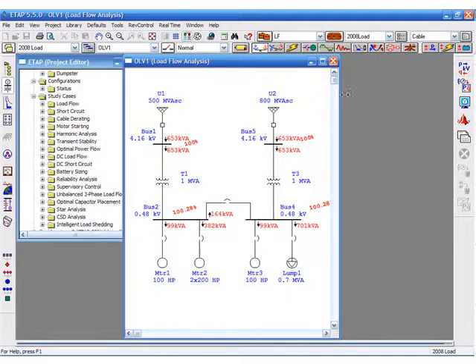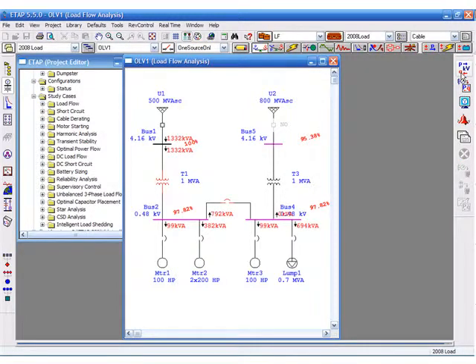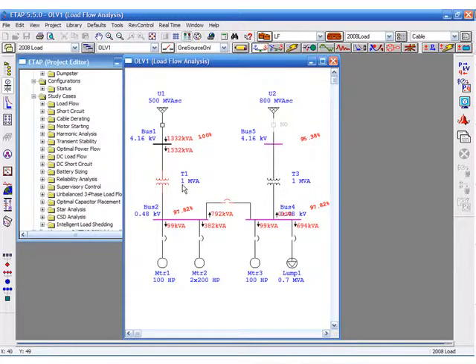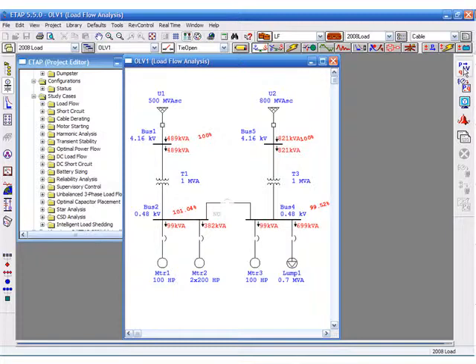We can now select the different configurations and analyze our results and how they pertain to the different operating conditions. You will notice the load growth exceeds the nameplate rating for one source only, but it does not overload the transformer when the tie is open.